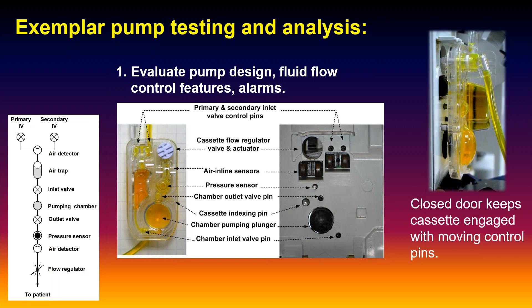We did some tests on the cassettes. There's also a sweet little valve that allows for fast flushing of the line out—it works like a regular needle valve. You can also just pull the valve out and cause the IV to free flow when you're setting it up and flushing the line. So characterizing that behavior was also something we wanted to find out.